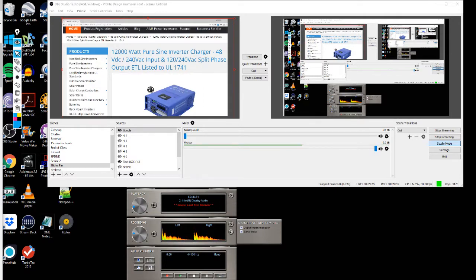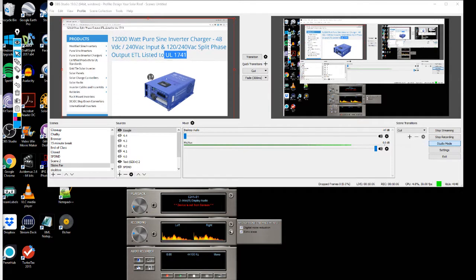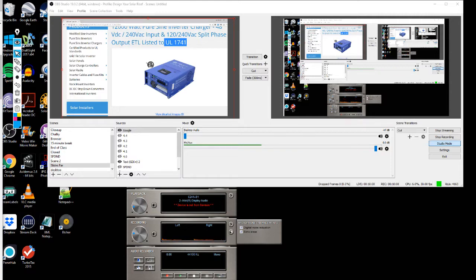Some jurisdictions will accept the ETL listing just as well as the UL. Other jurisdictions have been told they need to look for UL 1741, and they will not accept anything but UL 1741. But that's a grid listing, a grid-tied listing. If you're going to stay off grid, you do not need the UL 1741 listing.